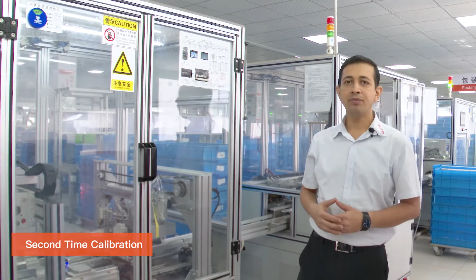Now we are at the second calibration of the RCCB testing. Between the first calibration and the second calibration, we follow a 5-day schedule. We follow this 5-day schedule because we allow the RCCB to cure for the aging, and we see whether there is any effect of the environment on the RCCB, inside the PMR or inside components, or not.